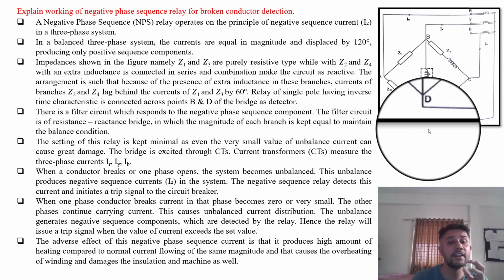The adverse effect of negative sequence current is that it produces a high amount of heating compared to normal current flowing of the same magnitude, and that causes overheating of the winding and damages the insulation of the machine as well as other components. So this is the functioning of the negative phase sequence relay for broken conductor detection.